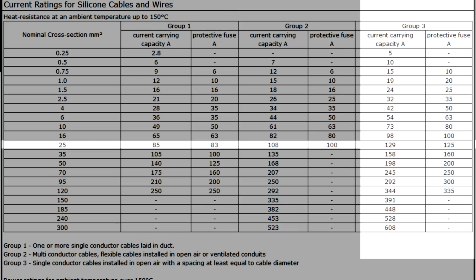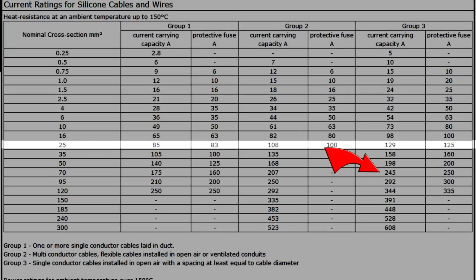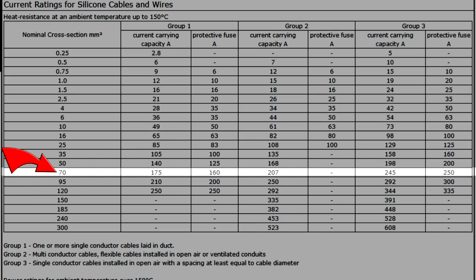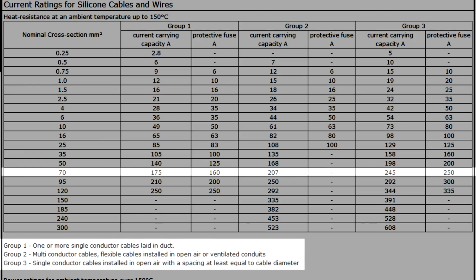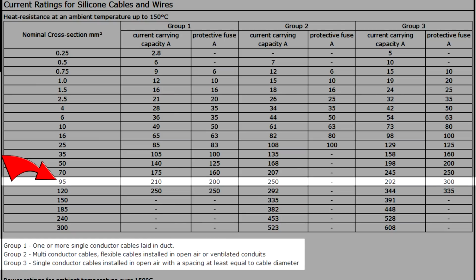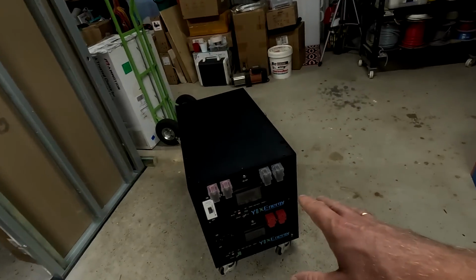But we are dealing here with 250 amps. So 245 here is at least a 70 mil cable, 3 times more than what they selected. But if you look for installation of these cables in tighter spaces, you need to go to group 1 or group 2. 250 amps demands at least a 95 millimeter cable or even a 120 millimeter cable. So this 21 or 25 millimeter cable they have used here is definitely not enough to carry 250 amps.